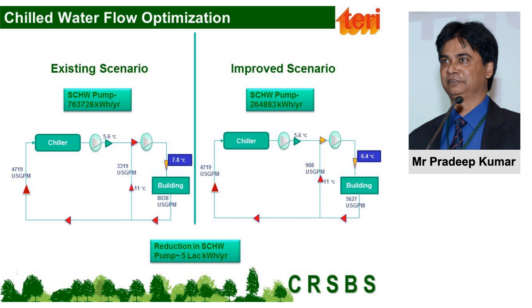And instead of operating at 50 Hertz, if it is operated at 35 or 37 or whatever we fix, almost 5 lakh units were saved. Doing nothing else, only this monitoring and changing the flow rate in the secondary line.